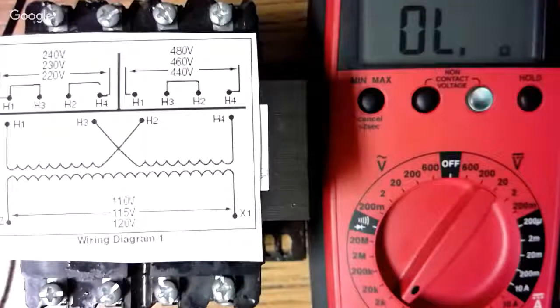Okay, unlike the simulator, in real life, remember this is one coil of wire. Your meter, when it is checking resistance, is putting out voltage. So if we have a coil of wire and we apply a little electricity to it, it's going to charge up, which means that we're going to have to wait for our meter readings to stabilize to get an accurate reading. So you can't always just check it right away.